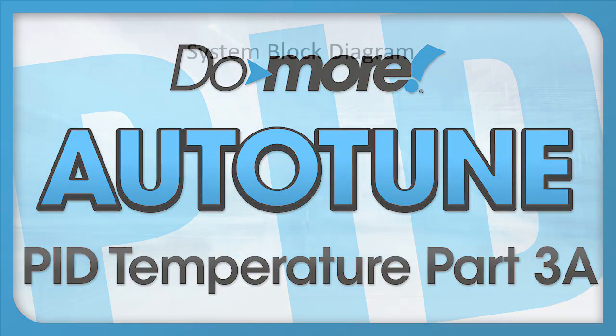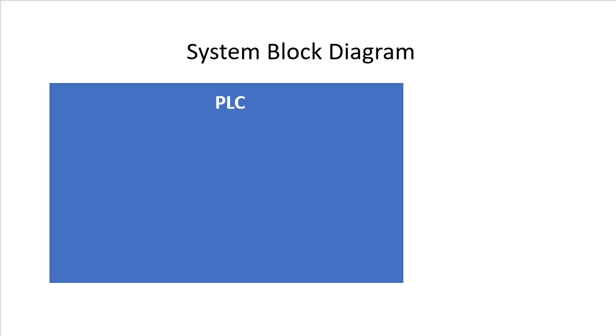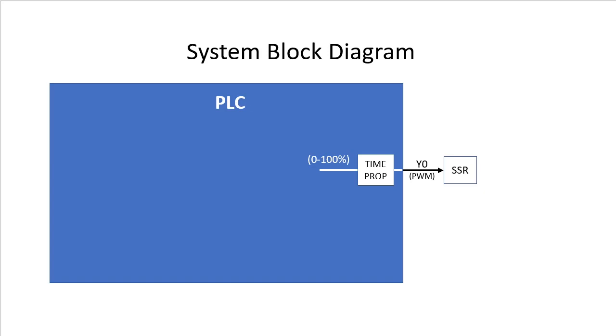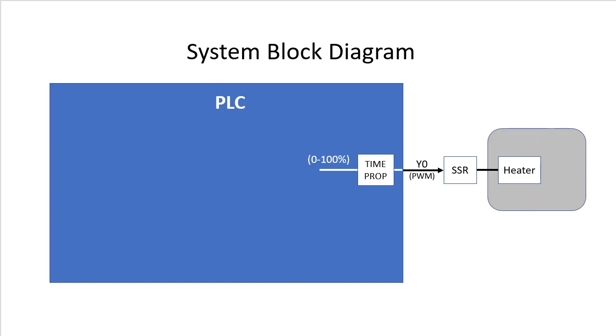Part 2 of this video series left us with a PLC that used the time prop instruction to create a PWM output on Y0. The PWM signal controlled a solid state relay which modulated the power input to a 500 watt heater which heated an enclosure that had room temperature air being pulled through it.